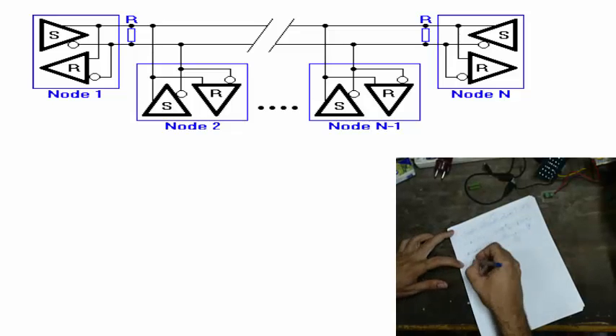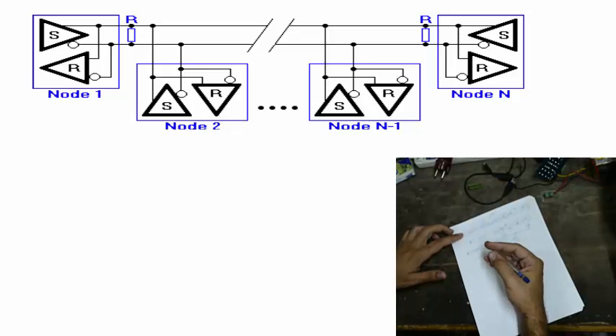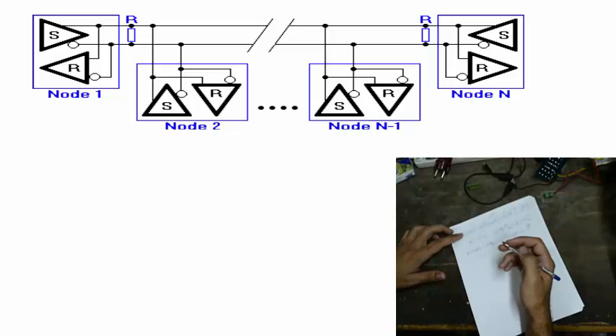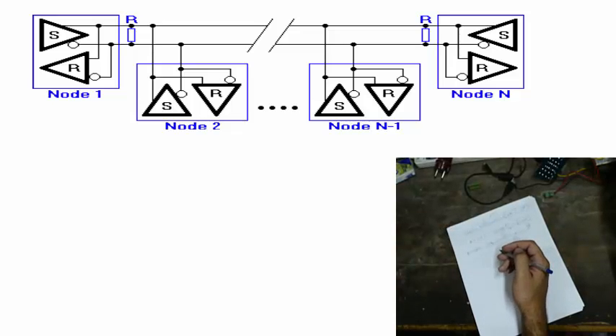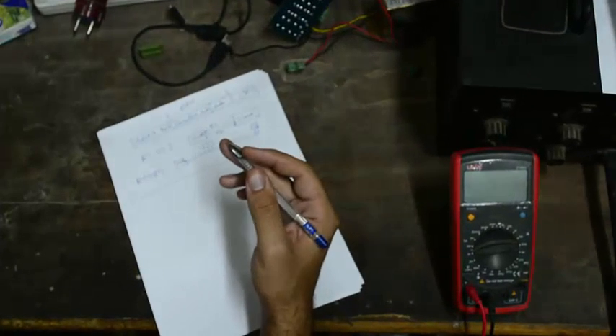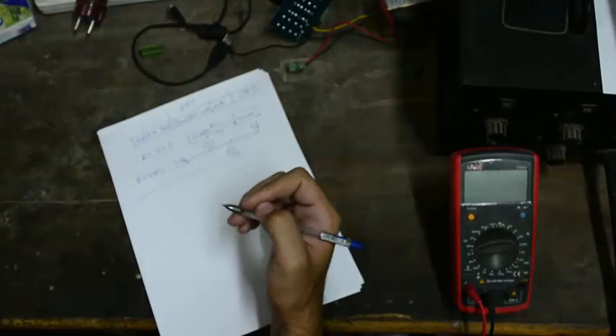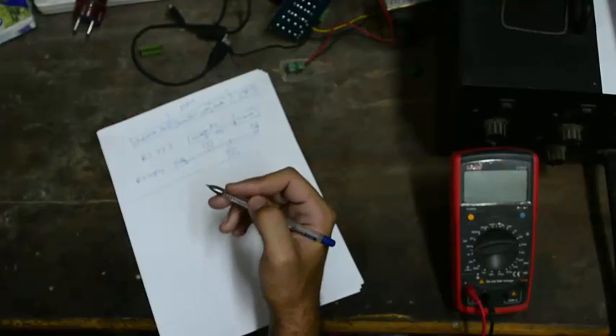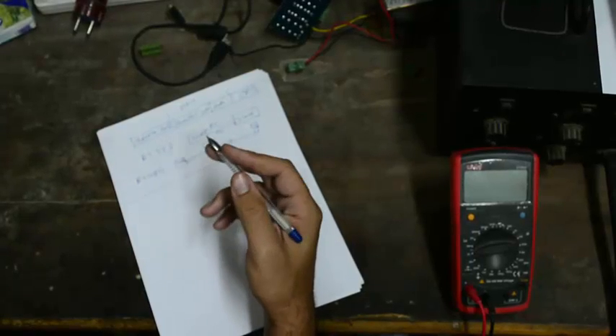The master places a value in the address field representing the address of one of the slaves, and the message is sent to that slave. The slave receives the message, analyzes it, and if there is no error, the slave responds with a response message. The master can also put zero in this field, which means it is broadcasting the message to all slaves in the network. If two or more slaves respond at the same time, the message will be corrupted, so you can't put more than one message physically at the same time on the bus.